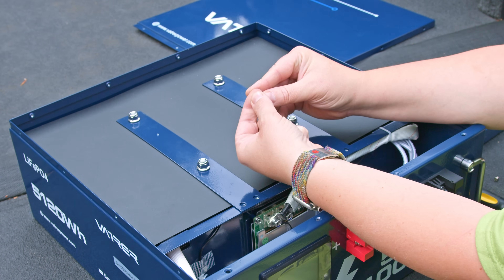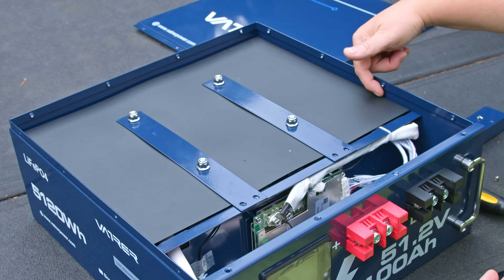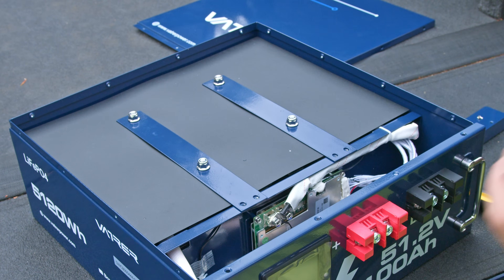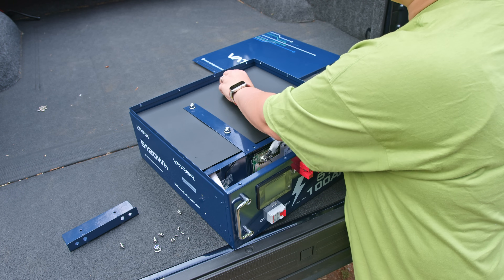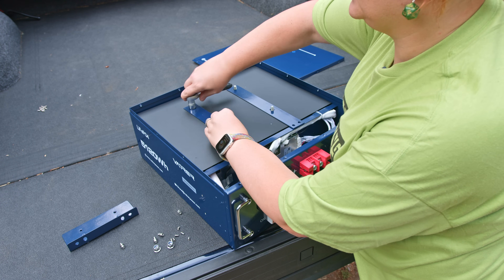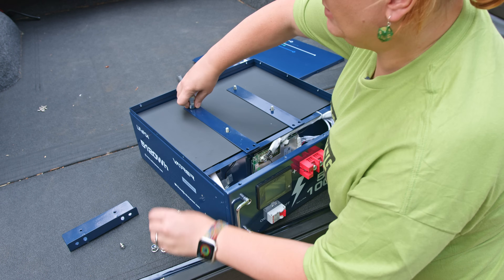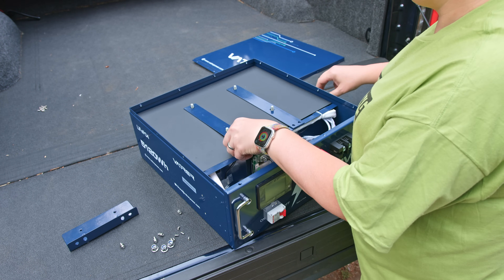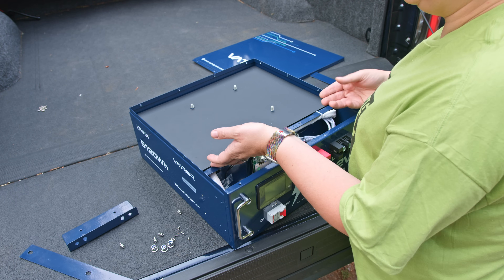I do want to highlight here that we've got some metal swarf inside the pack from the screws on the outside of the case — metal swarf that hasn't been filed off. You don't really want metal filings inside a battery, so I'm afraid that gets a down point for that. There are 14mm bolts on here that help hold these bars down and provide grounding to the bus bars inside the battery pack. There's also a sheet here that provides an insulative layer to make sure there's no short circuits on the actual cells. If it was anything more than 51 volts, I would be using high voltage gloves — and yes, 51 volts can still hurt if you short circuit, so just be careful. Again, I'm seeing some metal shavings there. Not so cool.